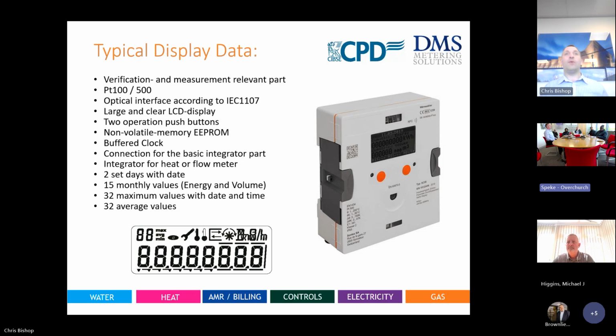If you've never seen a calculator, a display, an integrator, people use different terms. What a display does, again, is log the data. It does all the calculations. It gives you all the output. All the electricians wire up to there. All of the mechanical mount the display onto a wall, depending on who gets the job at the time. But generally, all our meters have a PT100 or 500 temperature input, which is a part of the Class 2 requirement. Yet again, we design that with the meter, with the application. Very simple. All meters have something called an optical interface.